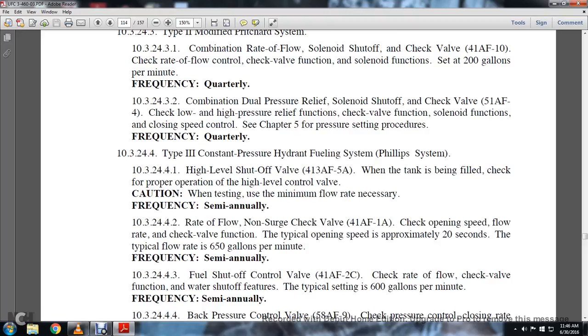In the Type 3 control constant pressure hydrant fuel system, the high-level shut-off valve is to be checked semi-annually. For the rate of flow non-surge check valve, check the opening speed for the flow. The rate check of the valve function, typically opening speed is approximately 20 seconds. The typical flow rate is 650 gallons per minute, semi-annually.